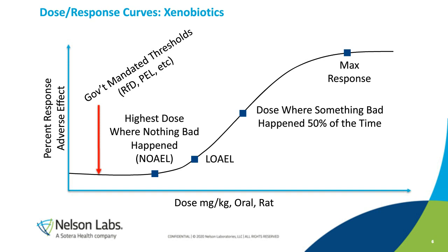When I say how much, I'm really thinking of it in a kinetic sense, where we're thinking about how much per day might be released by the device, because all of this tox literature is based off of total amount per kilogram per day. So that's the type of information that we look for, and that's exactly what we do when we conduct chemistry for medical device toxicology. We always have that in mind. It starts with this toxicological goal, and then the chemistry is a means to an end.